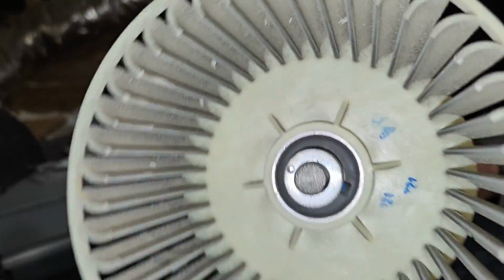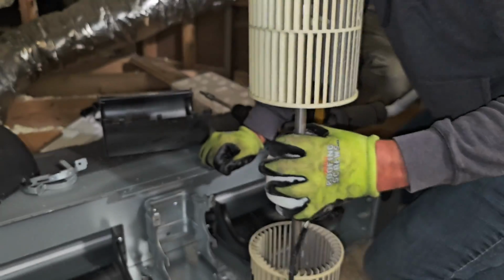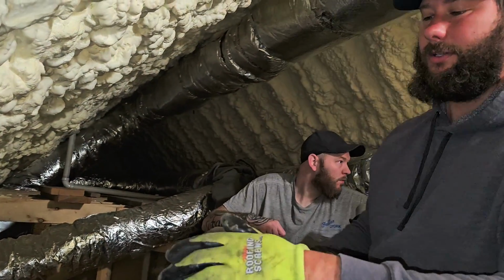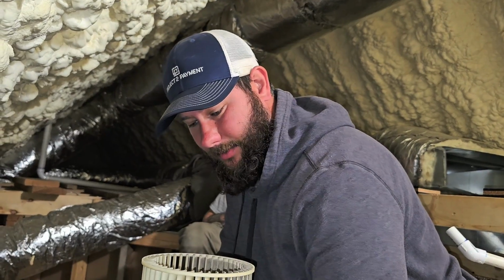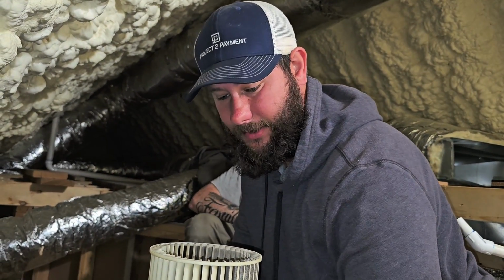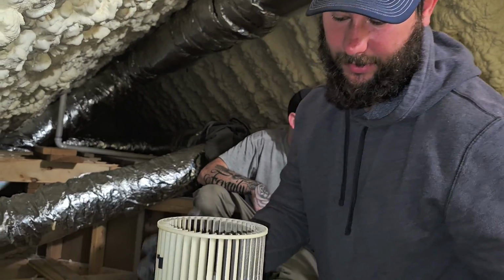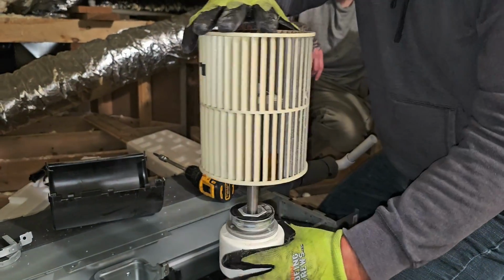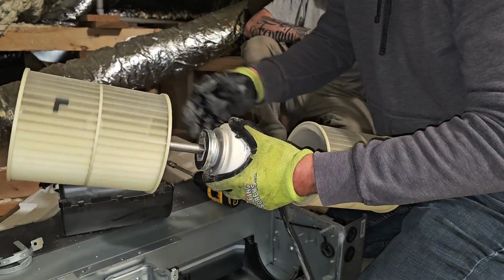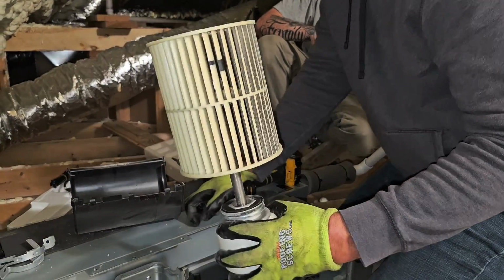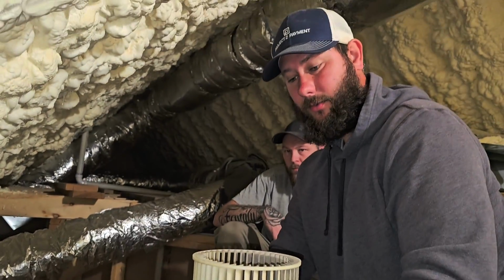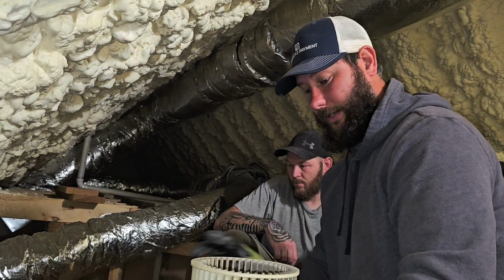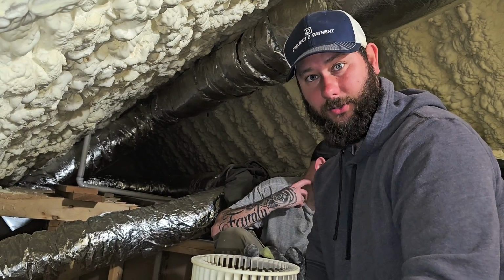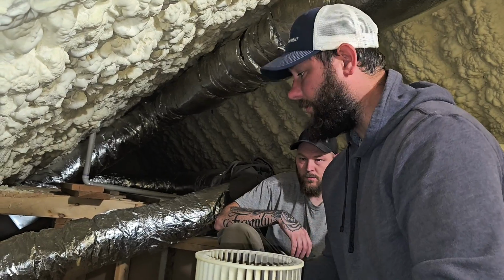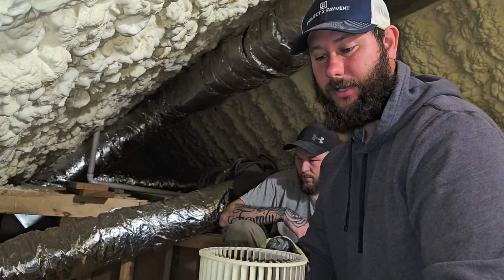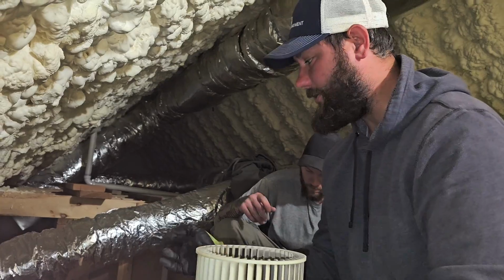You can see it's dirty, and that's the reason — when we did this job it was new construction, and I bet some of this dirt is from the construction process. We've got a set screw right there. All right, spins freely though, but it's making that noise. I'm going to take it outside, clean the wheel, and then put the new wheels on the motor. You can mark the old shafts with a marker and tape measure so you know where to tighten the set screw down on the new motor for the new wheels attached to it.